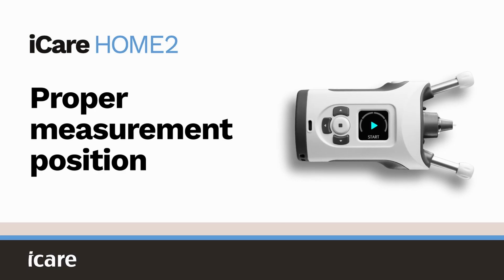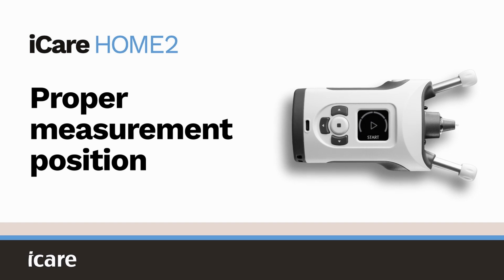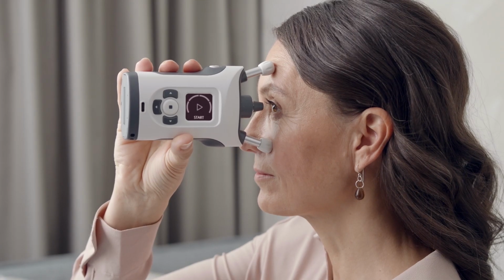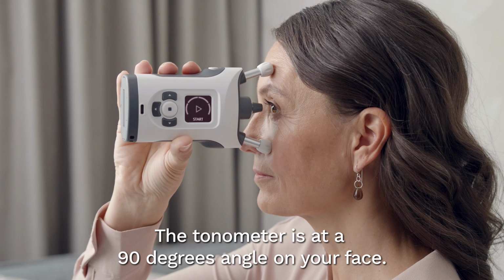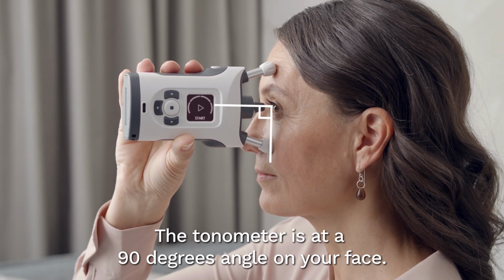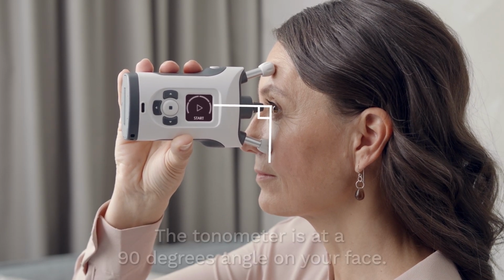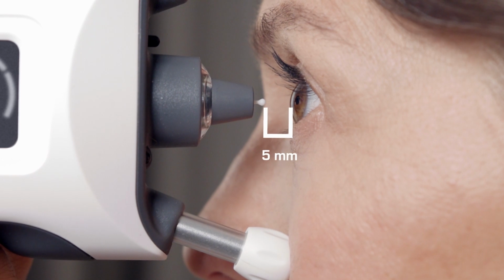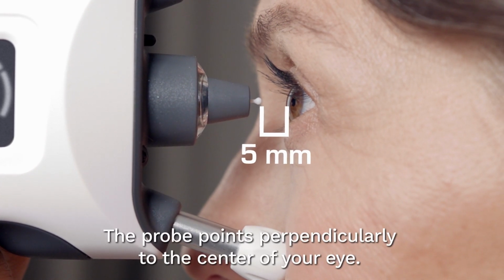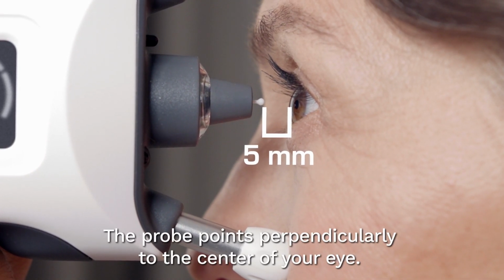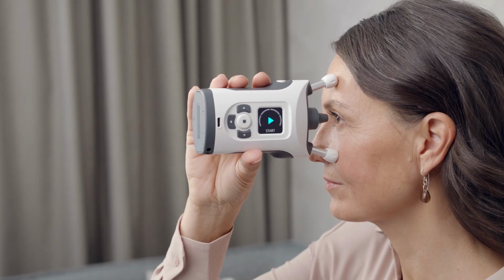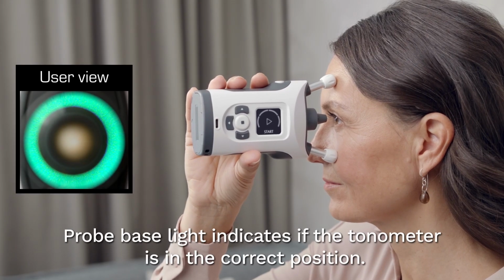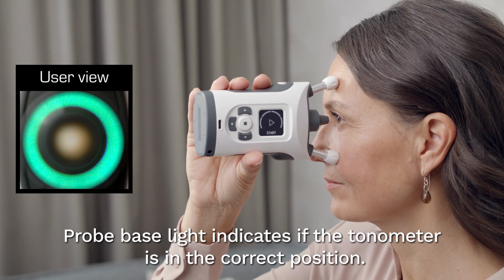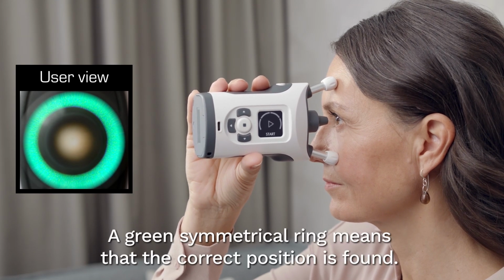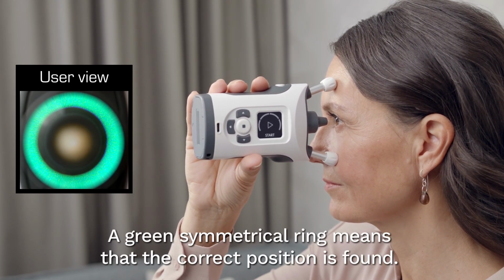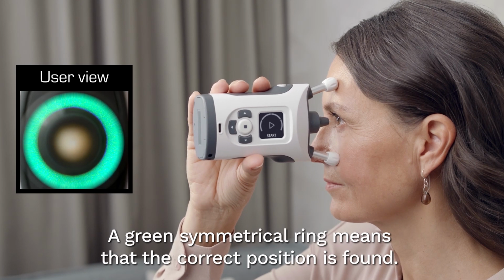Proper measurement position. In the proper measurement position, you look straight ahead and the tonometer is at a 90-degree angle on your face. The probe is about 5 mm from your eye and points perpendicularly to the centre of your eye. The probe base light indicates if the tonometer is in the correct position. A green symmetrical light ring means that the tonometer is positioned correctly.